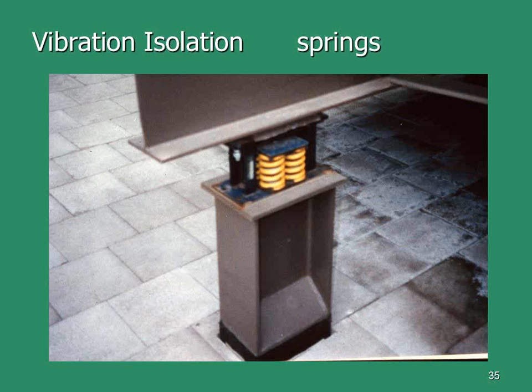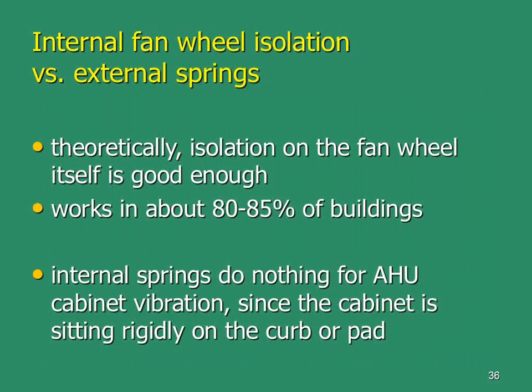It was quite the detective's science project. But once we got in there, we figured it out, cut a hole in the shaft wall, went in, and basically undid the turnbuckles about three turns so they were floppy. The noise went away. But you don't cut into the shaft wall in a fire-rated shaft in a high-rise building casually.